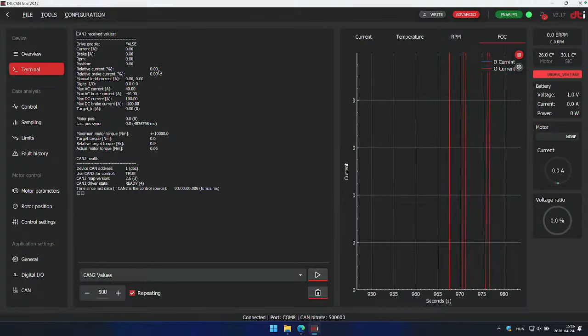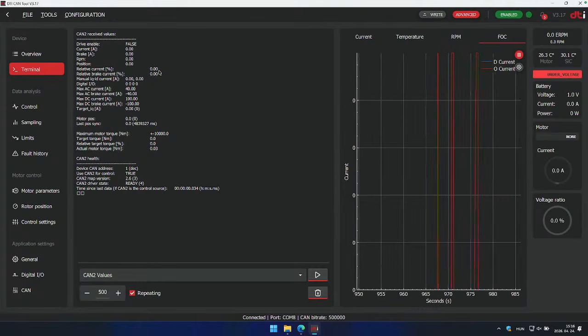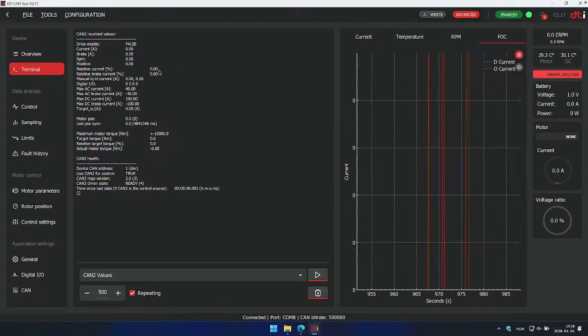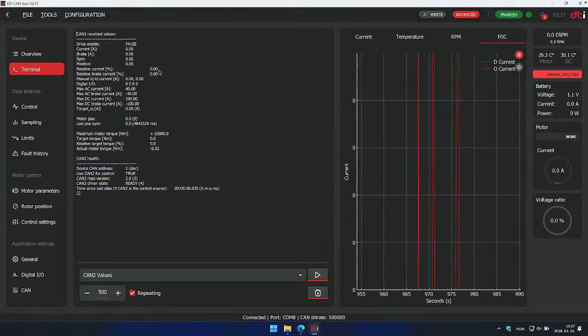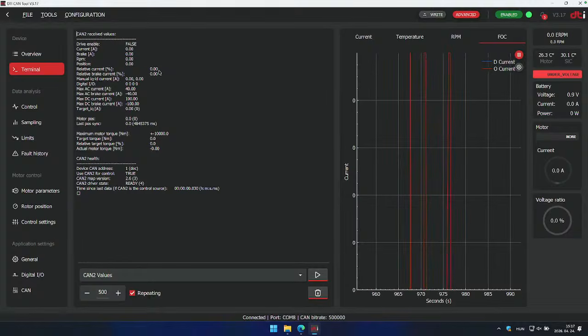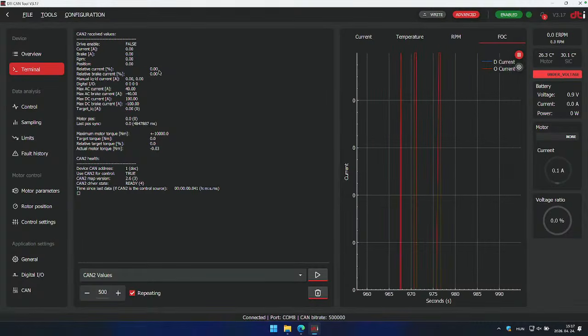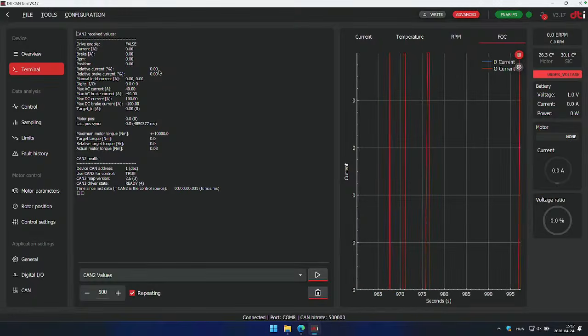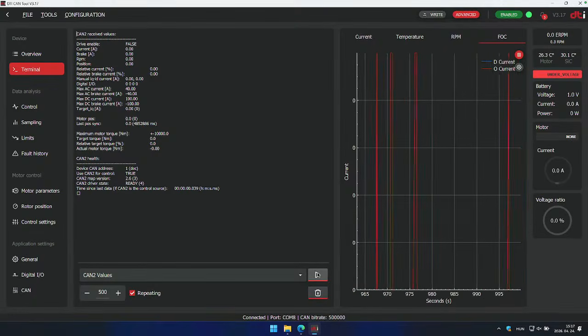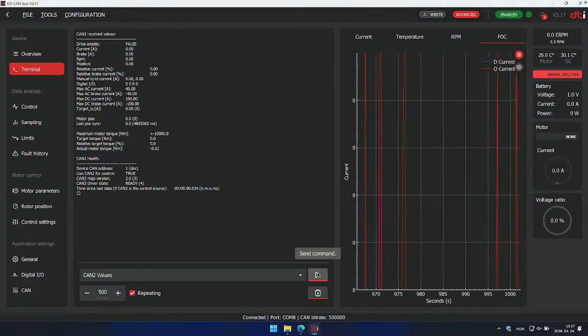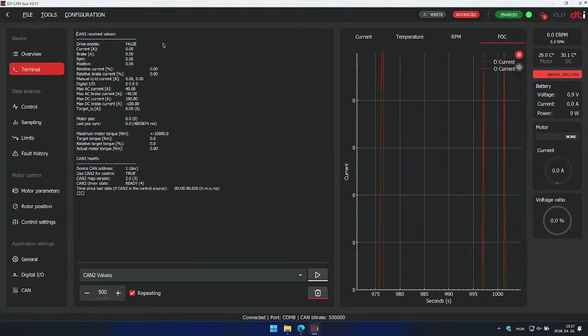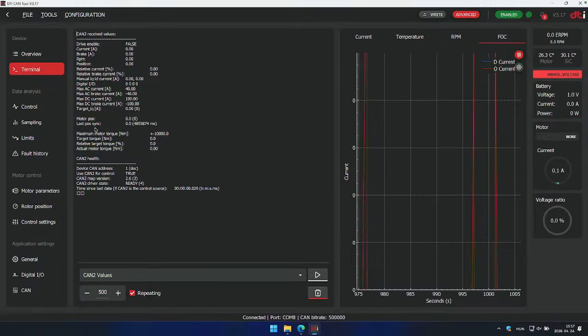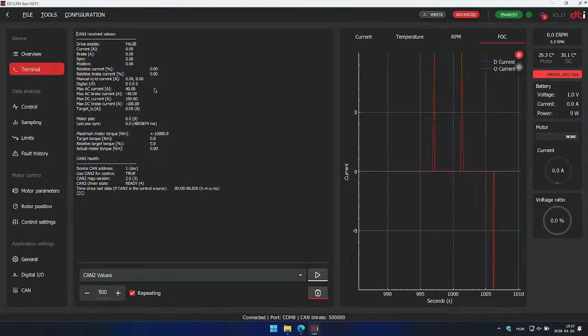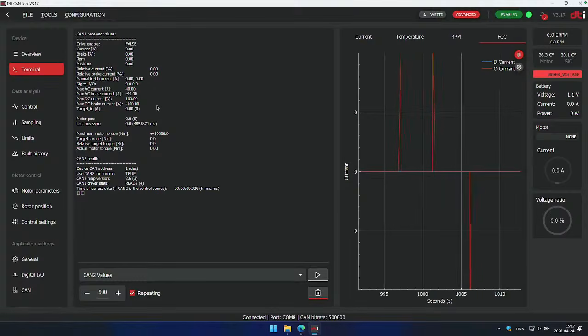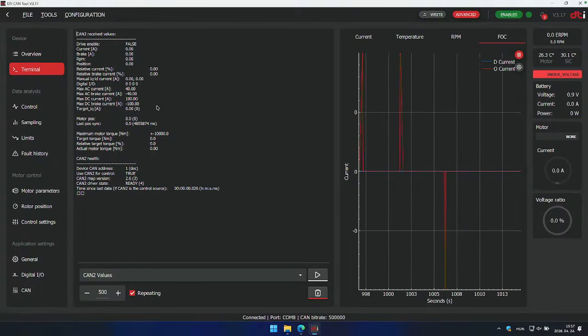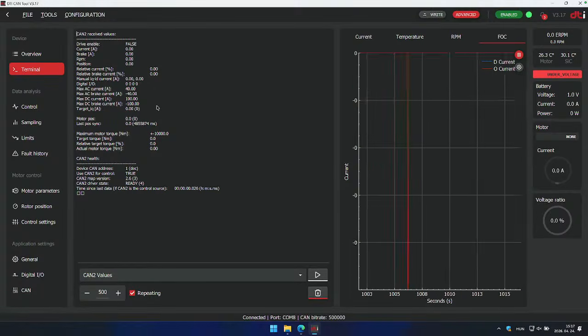The first crucial part when sending commands for the first time is making sure you have encoded in the right format and that the inverter decodes it in the right format. This terminal panel is a really good help for that, to monitor and observe the received current and command, and verify that it really matches the command you sent from your device.